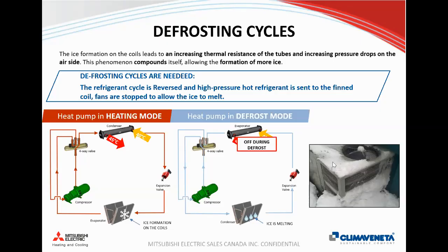There's been a lot of great strides within the industry from a lot of other manufacturers to have variable timing defrost cycles, simply put. So basically, modern defrost cycles will look at the ambient conditions and a few other parameters in the logic that I won't get into right now. If you're interested in that, feel free to reach out after the presentation. But essentially, by modulating the fixed timers, we can optimize our defrost cycles so that we're basically matching the conditions of the day, and we're only defrosting when it's truly required. So this is something to look out for whenever you're doing some selections for heat pumps and understanding the defrost cycles. But typically they'll only last a few minutes, and again, depends on the conditions.